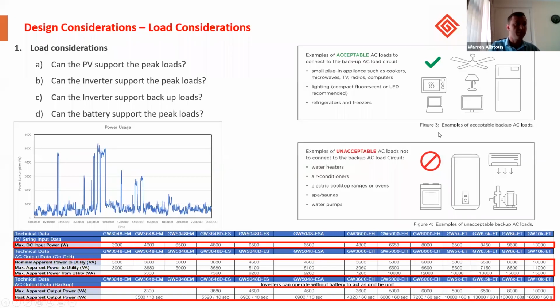Some examples of acceptable AC loads and unacceptable loads. Computers, TVs, lamps, ceiling fans, refrigerators, small cooking appliances, and freezers are acceptable. Some examples of unacceptable loads would be water heaters, air conditioners, electric cooktop ranges or ovens, spas, saunas, and water pumps, specifically water pumps without any soft starts. You have a very large start current.